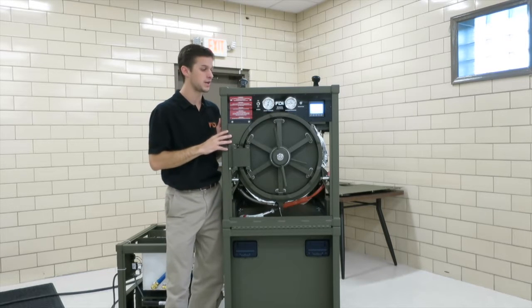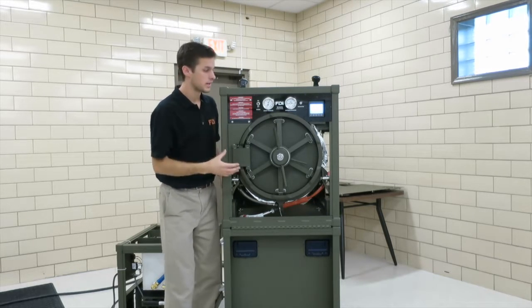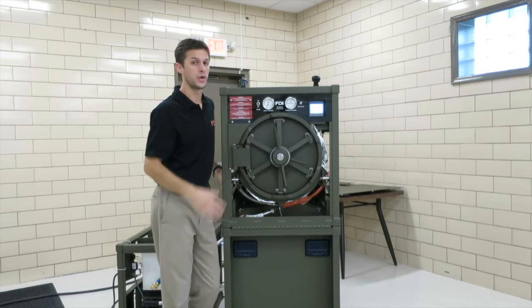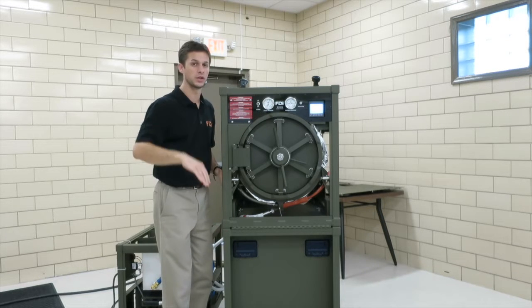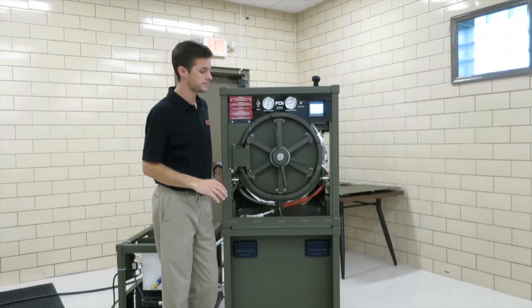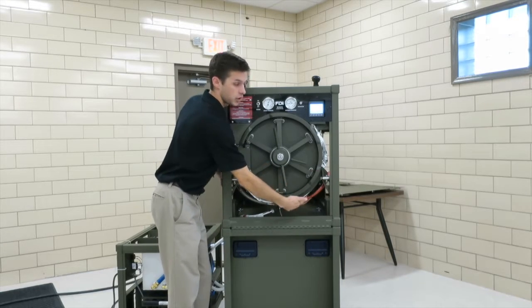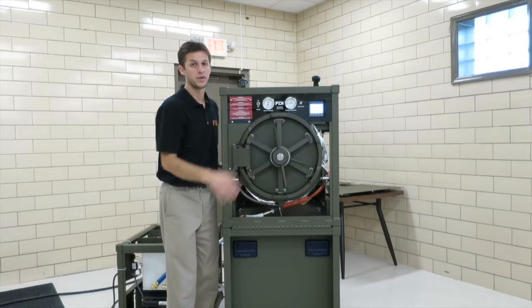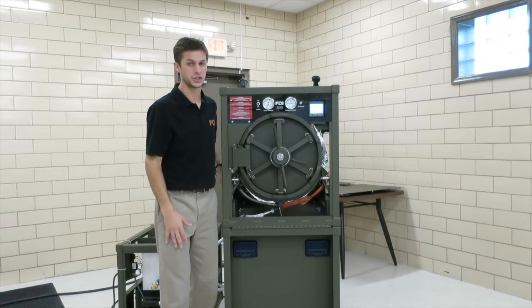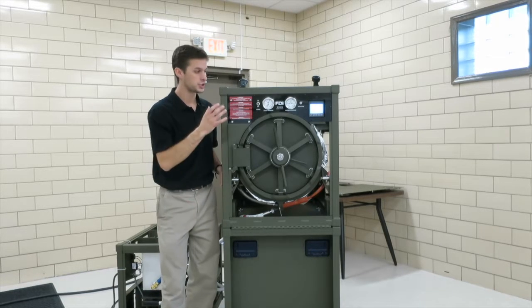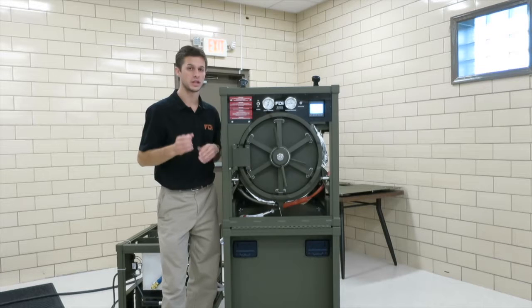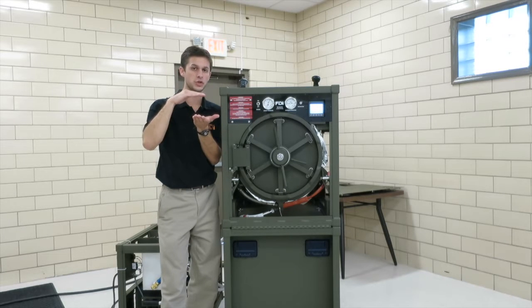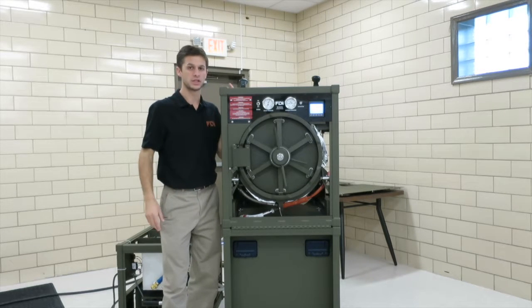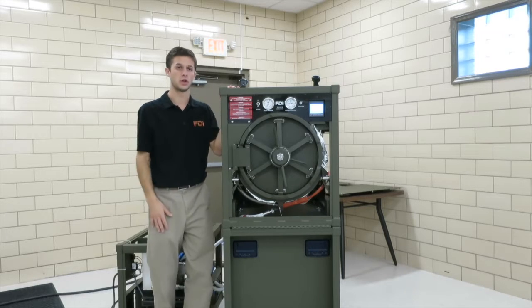And if this exposure time is taking longer than normal, the system may not be controlling well. So if it's constantly dipping below the set point, 273 degrees, you'll know that possibly the RTD probe is malfunctioning. Possibly the RTD transmitters are malfunctioning. So if the temperature equipment is not behaving normally and allowing it to find that set point, 273 degrees, you may get this long exposure time alarm.